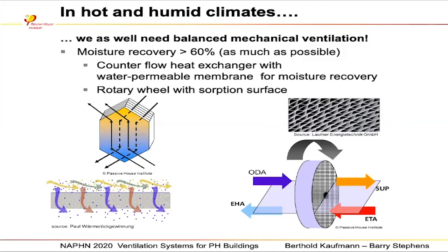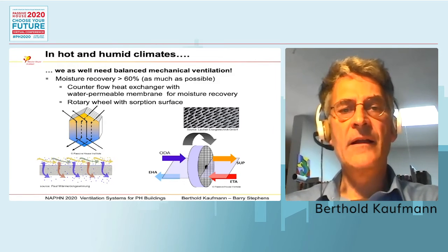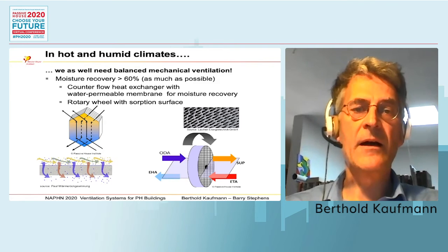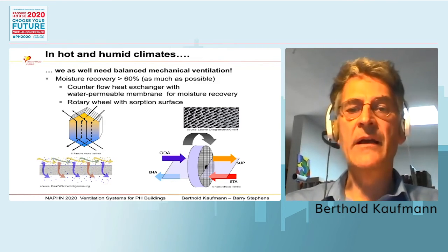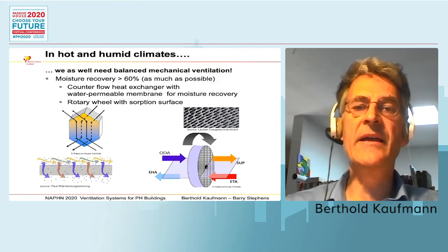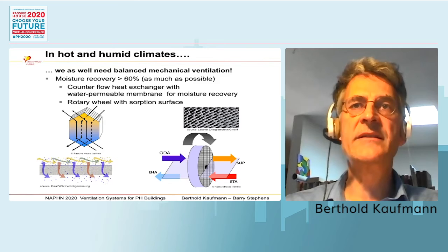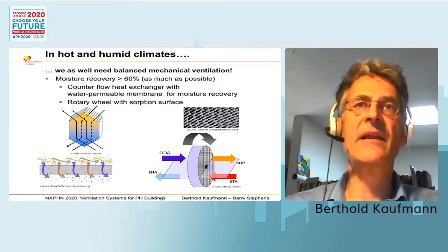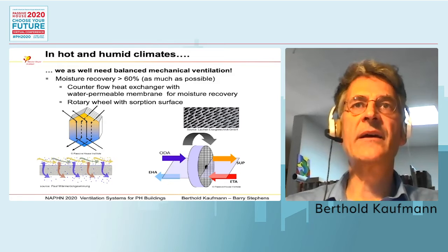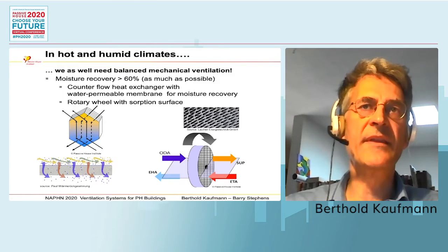And what is more, you can use in wintertime the effect that Barry explained: using an ERV or humidity recovery heat exchanger may allow for not so dry air indoors. Okay, on the left hand side, this is a membrane heat exchanger. The same effect can be reached with a rotary wheel, as with that, not only heat will be transported by the lamella, but as well water by adsorption or absorption on the lamella.